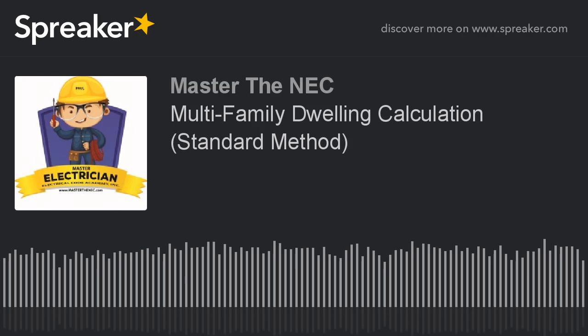So here's a couple things to remember. We have to make sure that we have a conductor that can actually handle this neutral load. But we are allowed to apply another derating value here. So this is where it gets interesting. Now, just so you understand, let's go to 220.61. Now we're dealing with the neutral. We already did the service conductor sizes. We're dealing with the neutral. We'll talk a little bit about neutrals here. All right, so 230.61, excuse me, what did I say? 220.61. Sorry about that. It's been a long day.